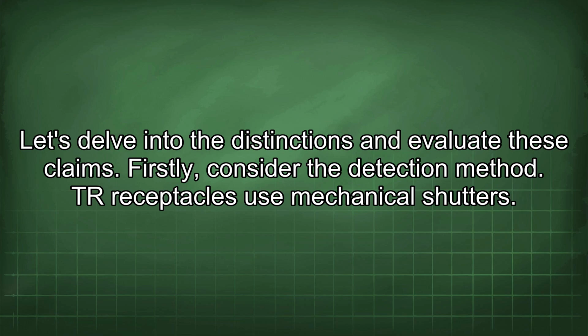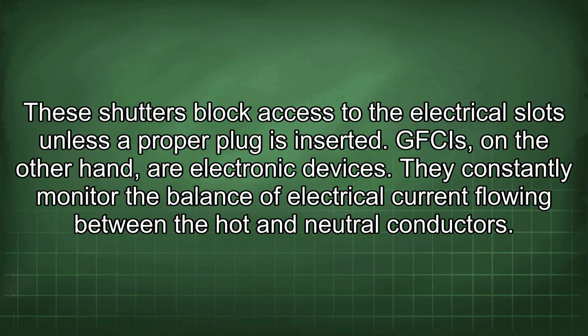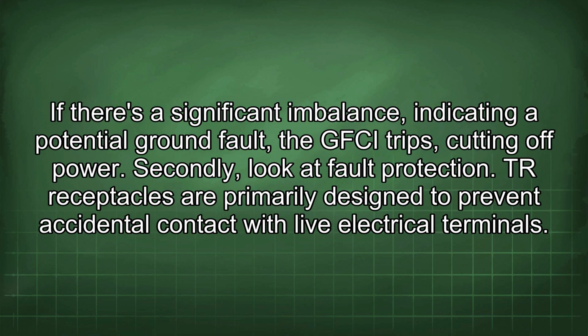Firstly, consider the detection method. TR receptacles use mechanical shutters. These shutters block access to the electrical slots unless a proper plug is inserted. GFCIs, on the other hand, are electronic devices. They constantly monitor the balance of electrical current flowing between the hot and neutral conductors. If there is a significant imbalance, indicating a potential ground fault, the GFCI trips, cutting off power.